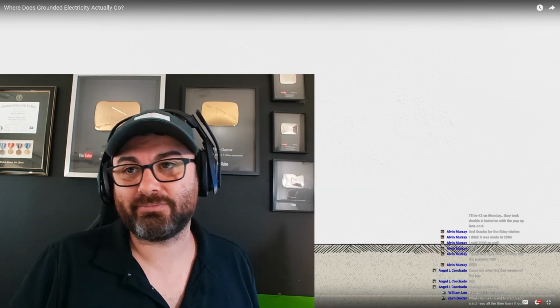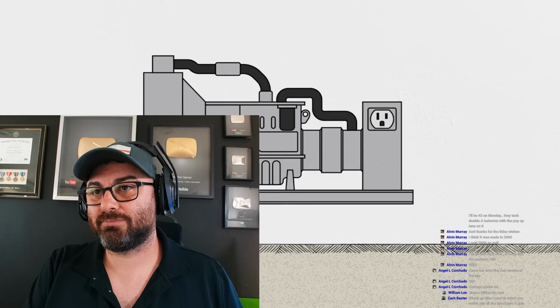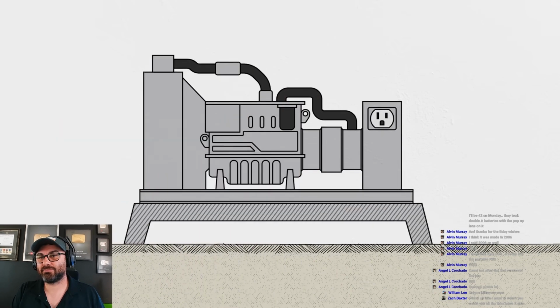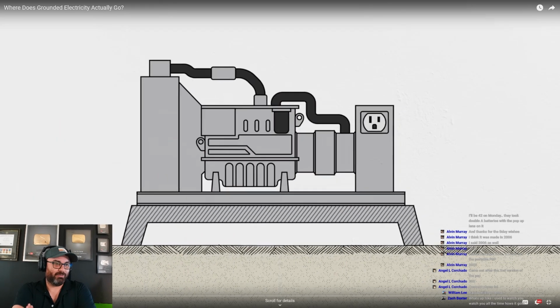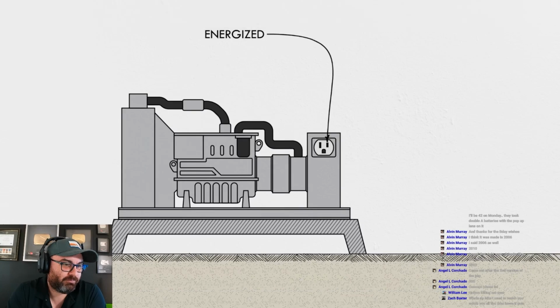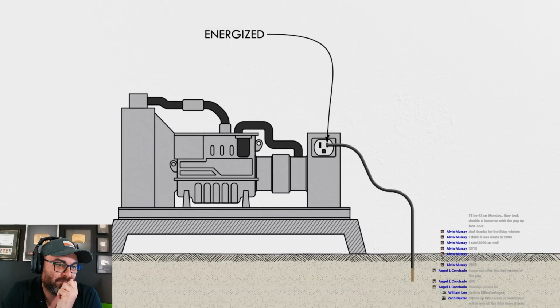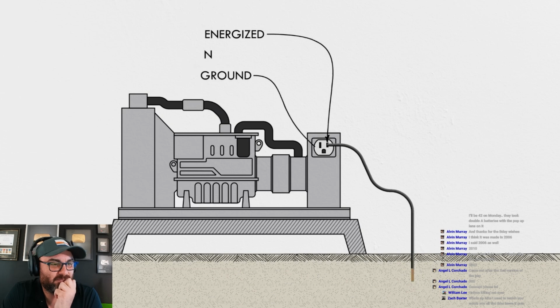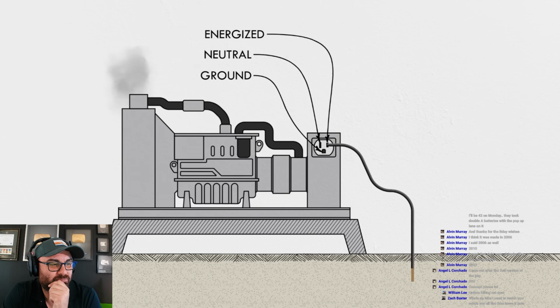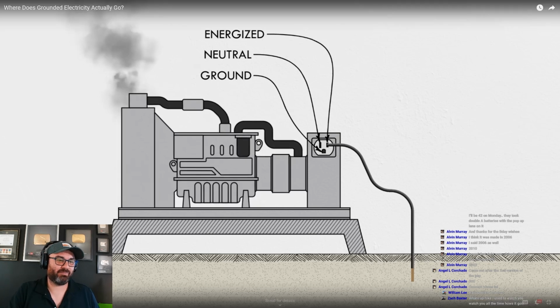Imagine this scenario. You have a diesel-powered generator on a stand that's electrically isolated from the ground. Run a wire from the energized slot of an outlet to an electrode driven into the ground. Don't connect anything to the ground or neutral slots. Now, imagine starting the generator. What happens? Does current flow from the energized wire?